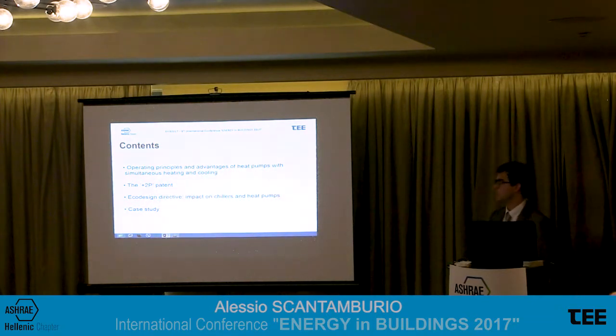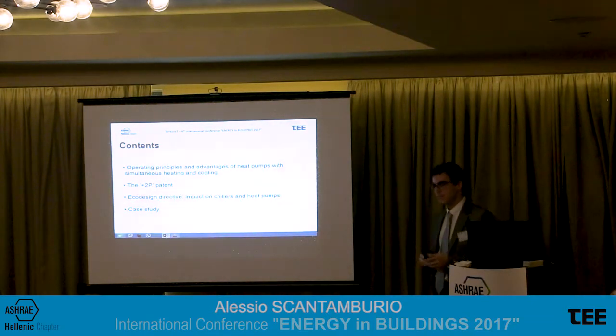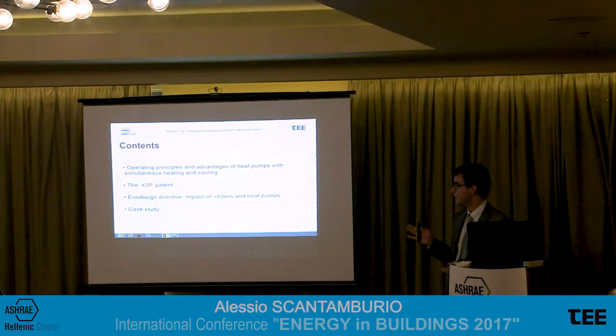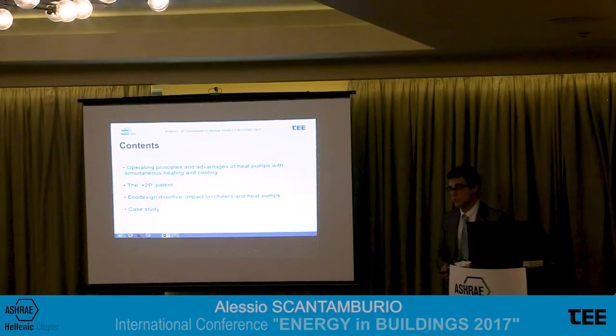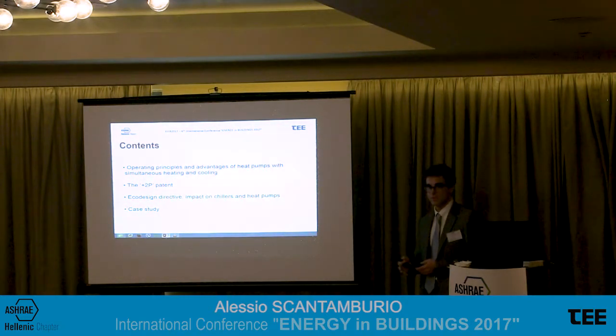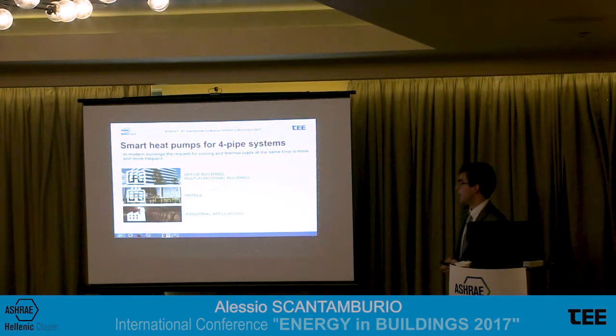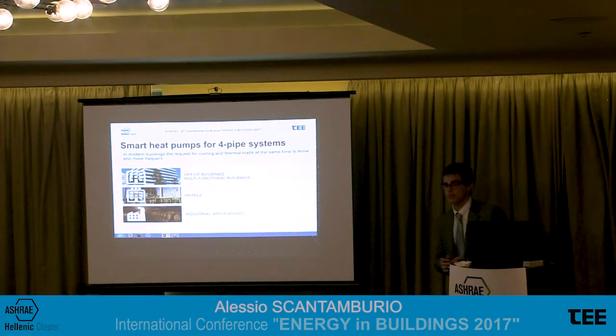The topics of these presentations will be an in-depth view of the technical content of 4-pipe smart heat pumps, and why they are different from standard chillers and chillers with heat recovery. Then an additional technology for producing very high water temperatures. Then a quick overview of the Eco Design Directive and its impact on chillers, heat pumps, reversible heat pumps and 4-pipe units. And then a case study to understand the efficiency of the 4-pipe concept compared to a traditional system. Starting from the beginning, just a couple of words about 4-pipe systems, 4-pipe plants.